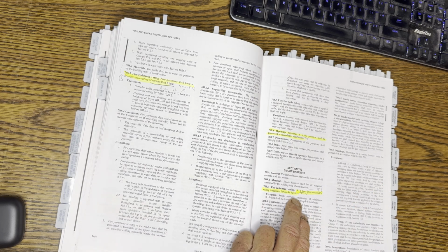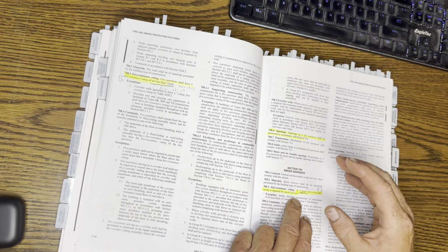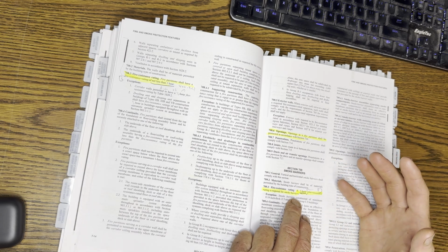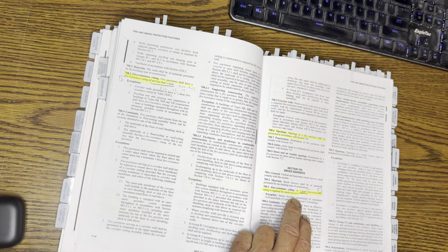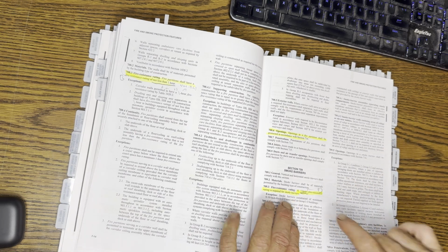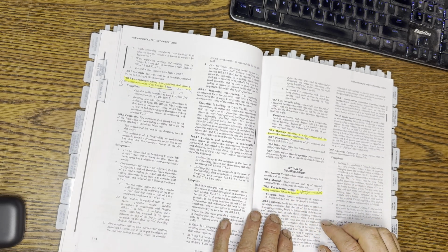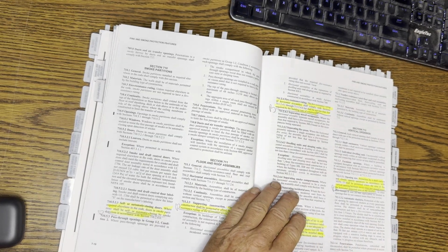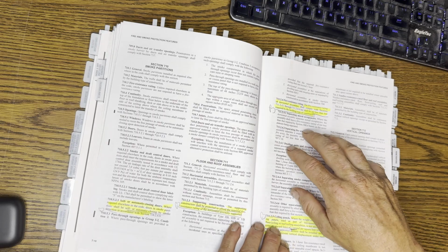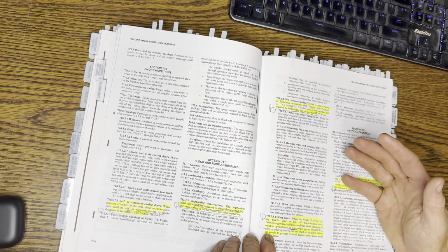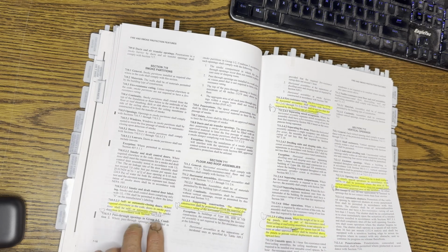But the problem with the furnace test is it doesn't reflect natural conditions for fire. A sooty environment is going to behave much worse than the vapors from natural gas. So these numbers don't correspond to real life survivability. They're just an apples to apples comparison for the sake of rating materials, not real life. So don't think that if I have a 1 hour rating, I'm going to survive for 1 hour. That's not the case. That's what I'm trying to explain here.